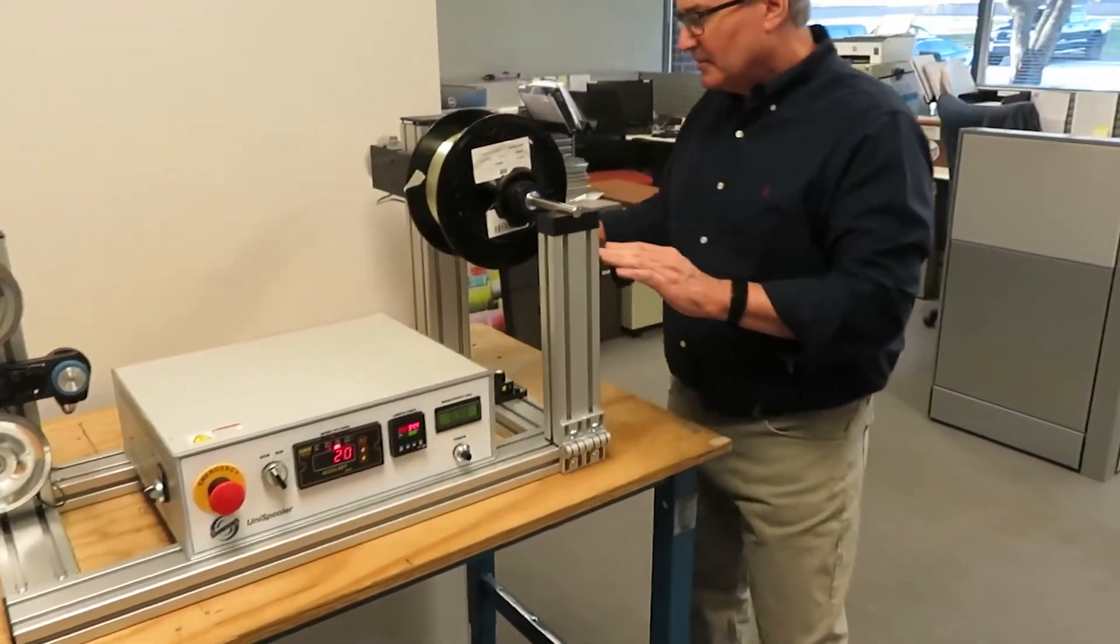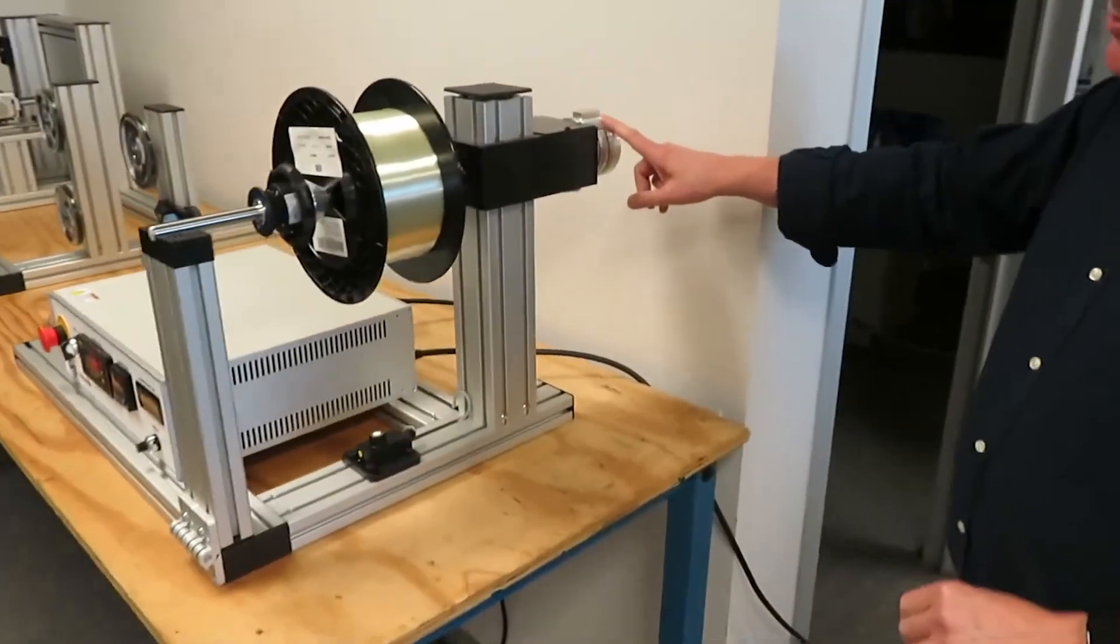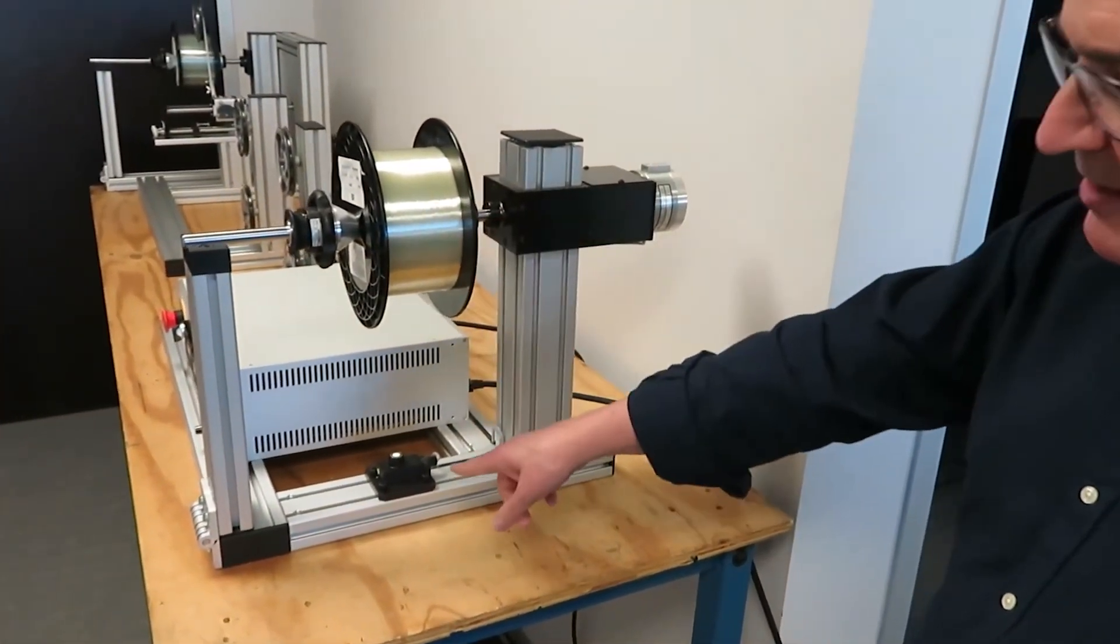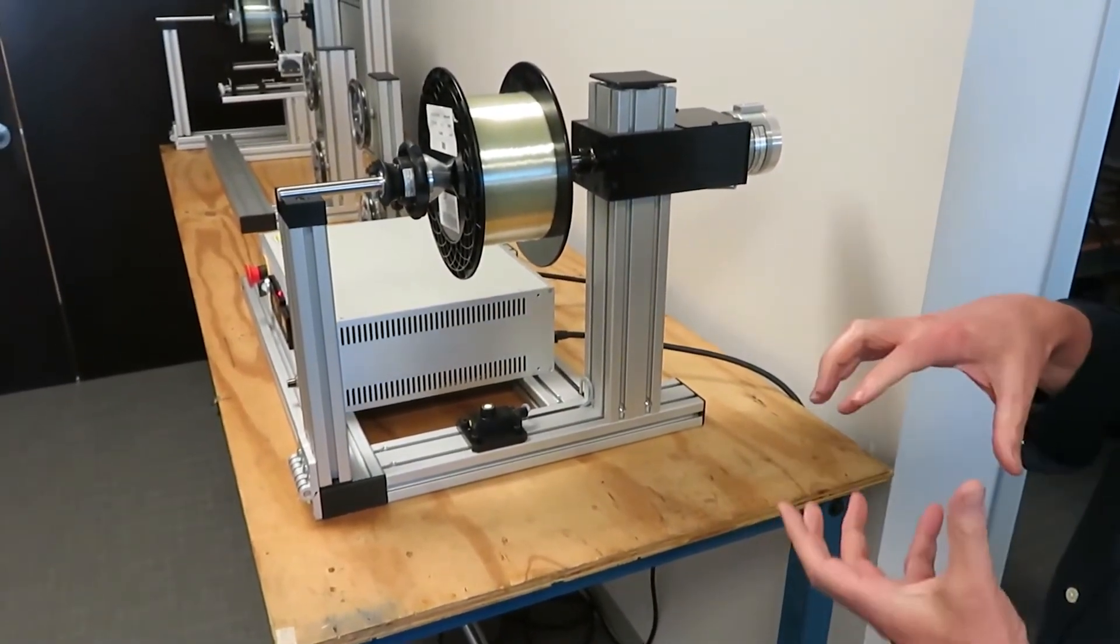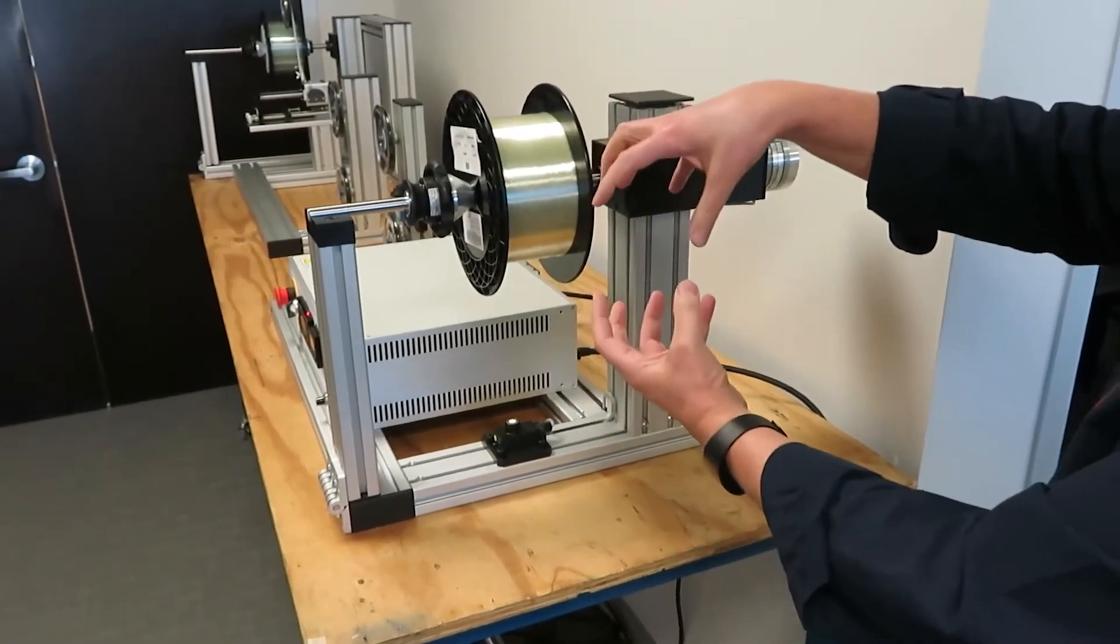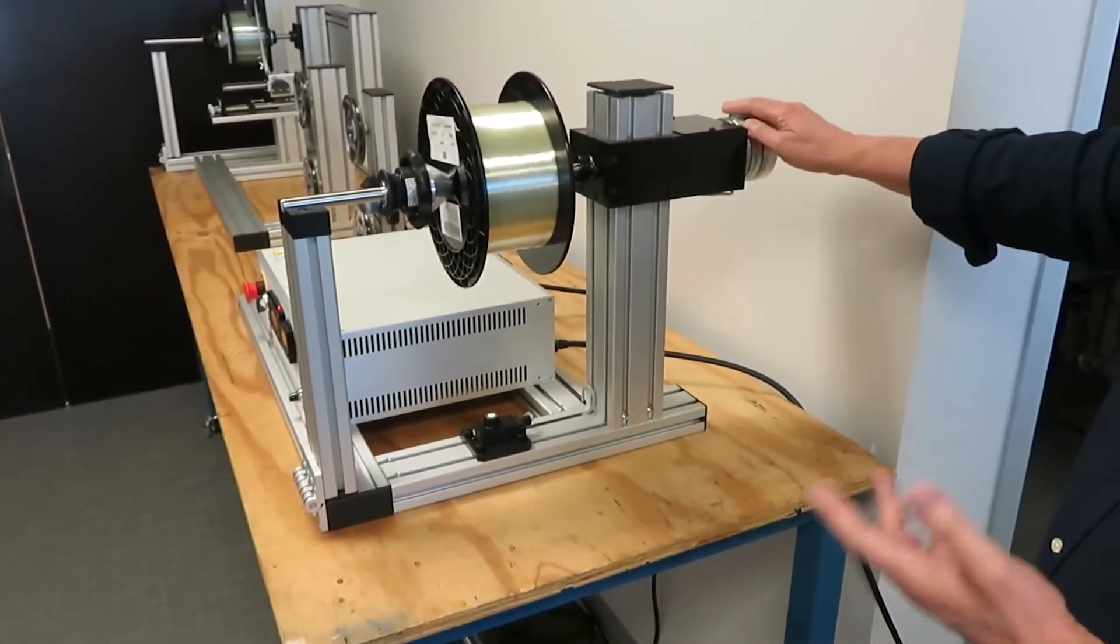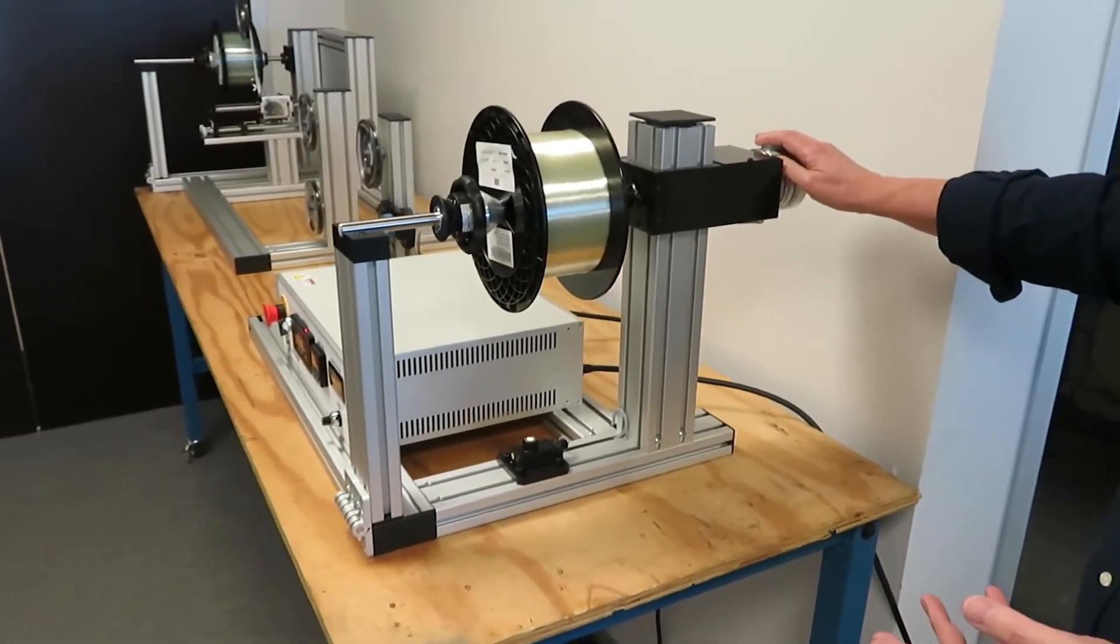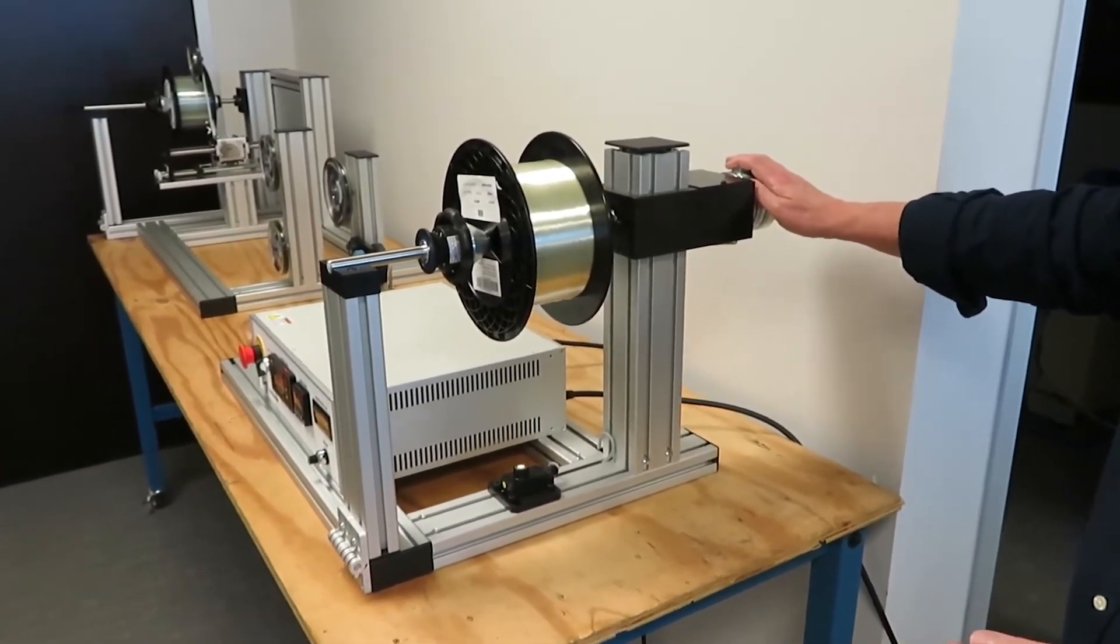We also have a closed-loop electronic brake on here where we're monitoring the diameter change of the payoff spool with an ultrasonic sensor below it that constantly monitors the diameter change and as that spool gets smaller it'll lower the amount of current going to the brake to reduce the amount of torque generated by the brake with the goal of maintaining constant tension. It does a pretty good job of that.